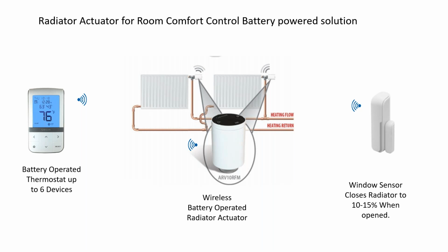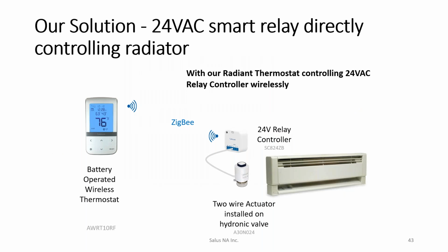Also, the battery operated thermostat can be placed on an interior wall, which gives you a much better measurement of comfort in the space, and it will shut down the flow of heating water through the radiators, and allow that energy to be recaptured and sent to other areas that may need it, which will in turn give you an efficiency. Also, we have window sensors, which will close the radiators down to 10 to 15%, so you don't have a damaged system, but it will make the space cooler, and hopefully they'll close their windows and comply with the rules.